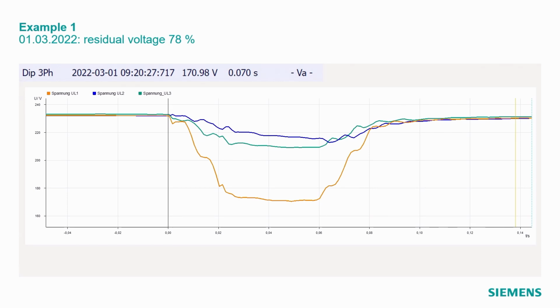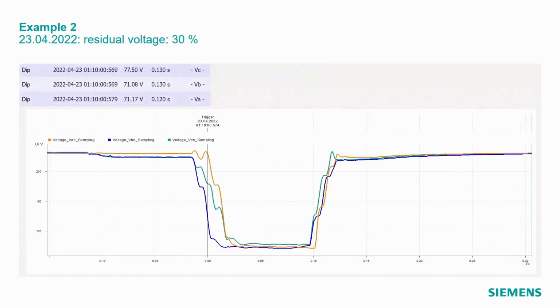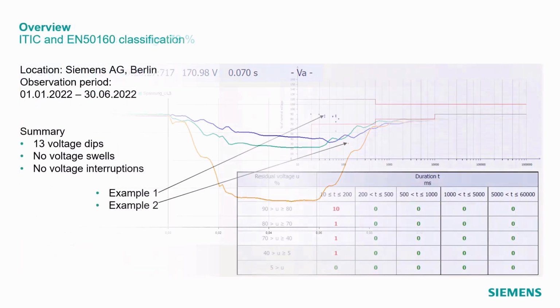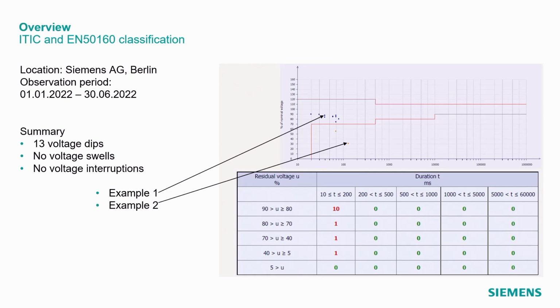It's a little bit different in the application example 2, because you see the RMS curve here. This event occurred on 23rd of April in 2022, and the residual voltage in all three phases is only 30%. That means for 130 milliseconds, phase A, phase B, and phase C voltages were only 72 volts. And if we go back to the ITIC curve with the evaluation result, you see that it's outside the ITIC curve. And that could be a problem for some equipment in this low voltage installation, because it can lead to interruption of some devices or data communications and so on. I don't have the details, but it's quite a heavy power quality event here.